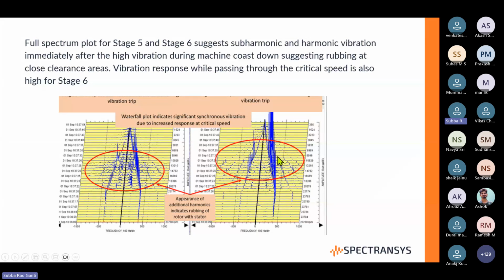So this is typically a situation generated by the rubbing of the rotor. When the machine tripped for whatsoever reasons, while it was coasting down, at certain locations the rotor was rubbing, and that rubbing action has created this harmonic content. You can see that it did not exist before the rubbing. It existed only while the rubbing was happening, and when the rubbing finished, it no longer exists. And here also you can see the forward components and reverse components.